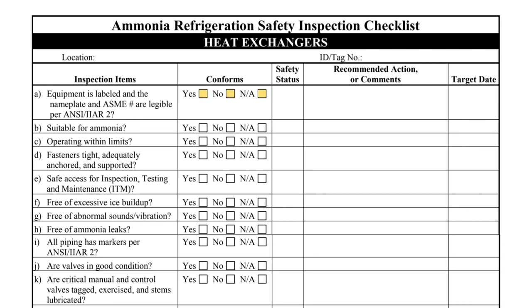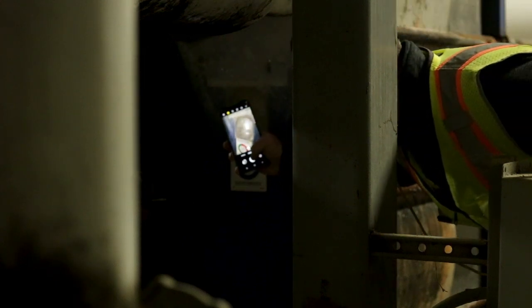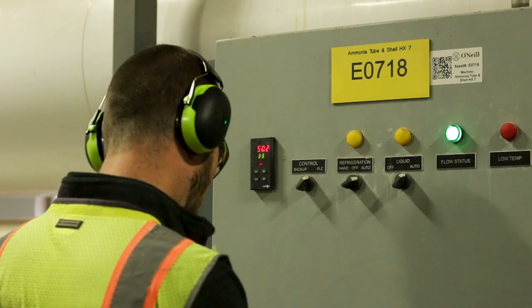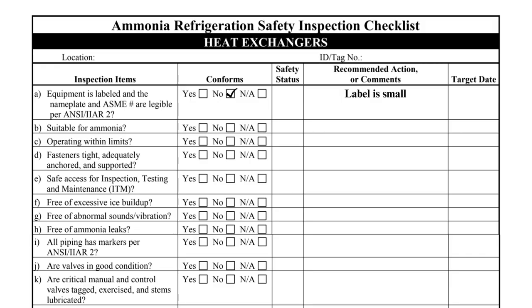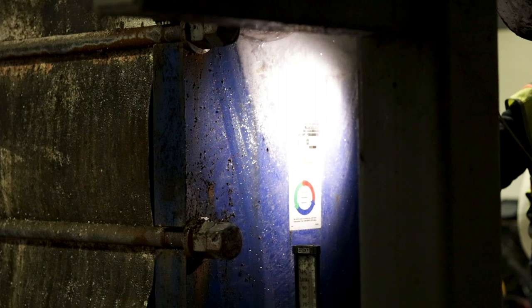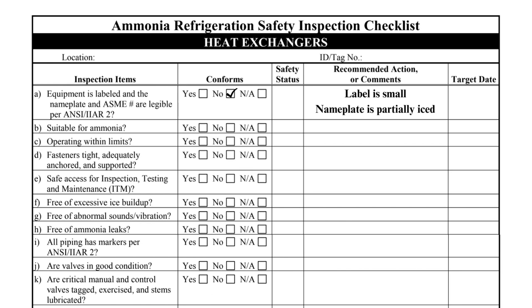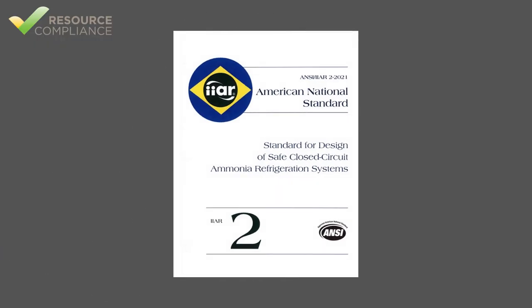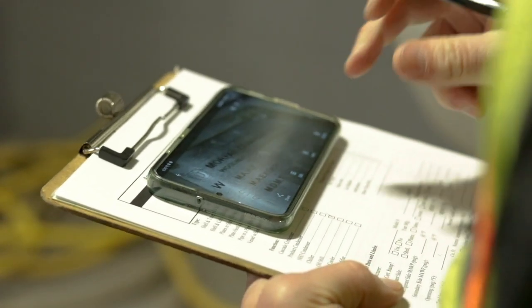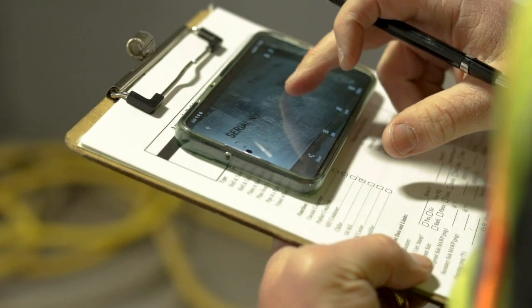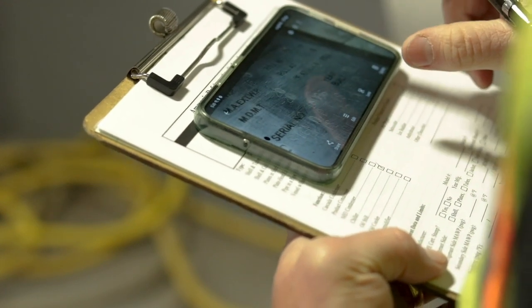Item A asks if the equipment is labeled and has a legible nameplate. A proper label consists of the component name and ID number. Since this shell and tube heat exchanger label ID number is so small, that should be marked as an item to be addressed. The plate and frame heat exchanger nameplate is partially iced — this is not a deficiency but should still be indicated as a comment on the checklist. IIAR Standard 2 contains the requirements for heat exchanger nameplates. If the heat exchanger is ASME stamped, the nameplate must comply with ASME requirements and contain all of the information required for pressure vessels.